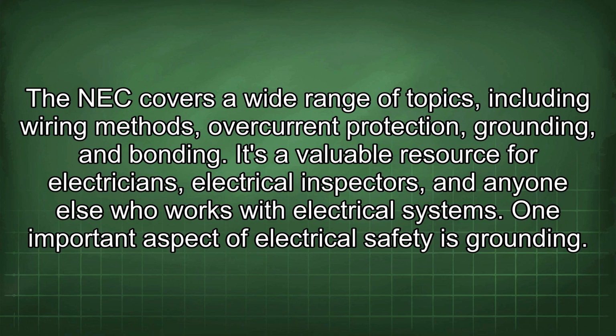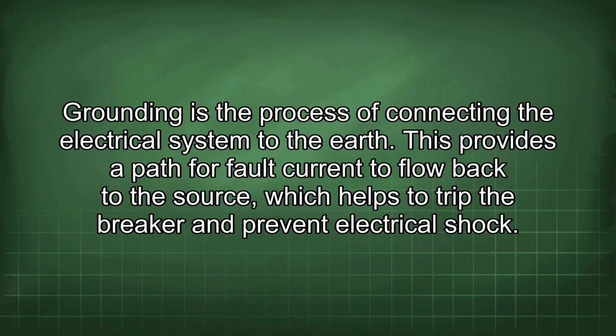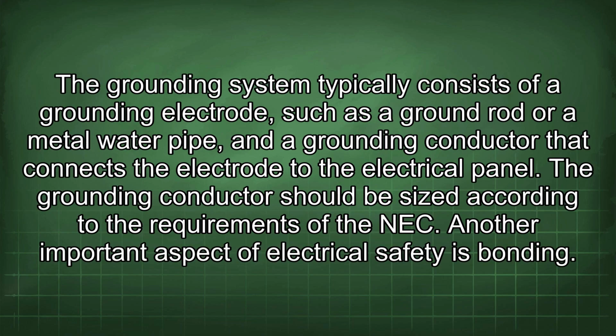One important aspect of electrical safety is grounding. Grounding is the process of connecting the electrical system to the earth. This provides a path for fault current to flow back to the source, which helps to trip the breaker and prevent electrical shock. The grounding system typically consists of a grounding electrode, such as a ground rod or a metal water pipe, and a grounding conductor that connects the electrode to the electrical panel. The grounding conductor should be sized according to the requirements of the NEC.